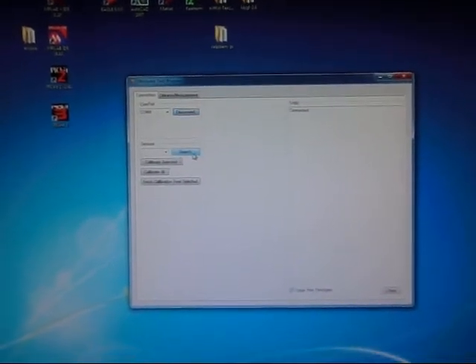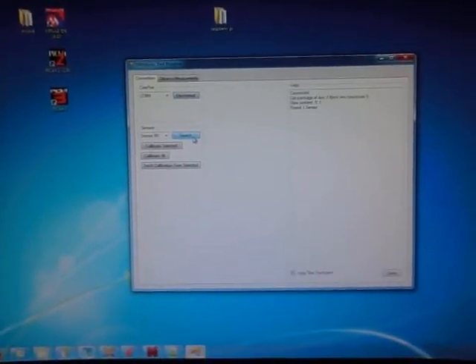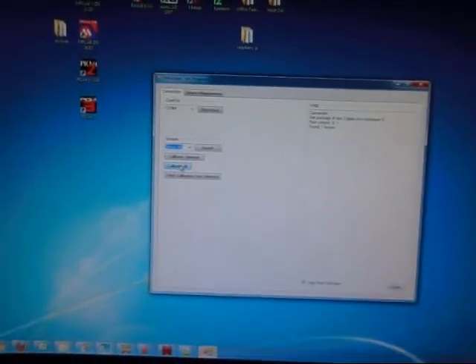So I have written a program for a PC in C#. I don't know if it's focusing, but basically I can connect and then I can search for the sensors, and it's only found one sensor in the net, and I can then calibrate that sensor, which it is now doing. It will take some seconds and then it will be done. I can then retrieve calibration from the sensor, and here we can see the vector that is calibrated.